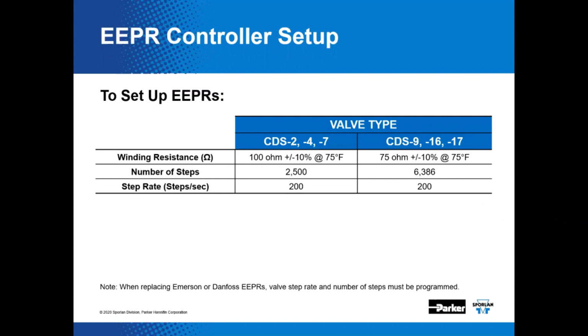Sporlan valves are typically designed with a 200 step per second step rate. And then, of course, the resistance varies based on the number of steps in any given valve design. This is a pretty good time to point out the number of steps, particularly on those larger models, 6,386 steps. That's a bunch of steps, and it facilitates some very fine control of those valves. So that's just one of the things you can look at that tells you that these valves are capable of some very precise control.